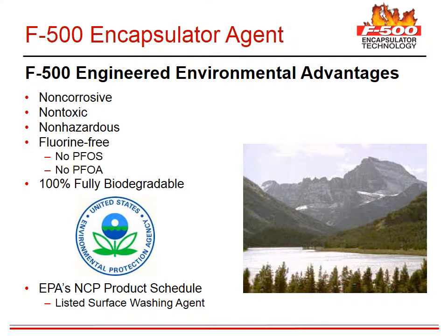In the firefighting business, we always have to be aware of what we do to the environment. Using F500 allows us to mitigate many hazards and yet be environmentally responsible. F500 encapsulator agent is non-corrosive, non-toxic, non-hazardous, and 100% fully biodegradable. F500 has been listed by the US EPA as a surface washing agent for fuel spills on roadways, on the shore, shoreline, rocks, pilings, piers, and wharfs to encapsulate and render them non-flammable.